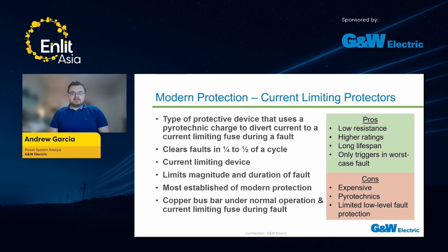These can go up to much higher ratings than the solid state breakers or the current limiting fuses can. So a lot of times it's between this and reactors at higher levels of ratings. They have a long lifespan. It's a very simple but genius electronics and pyrotechnic device, so it can last 20 years plus. And since it's electronically activated, it's only going to trigger in the worst case fault scenario. So you don't have to worry about any kind of nuisance trips, say like with current limiting fuses that lack flexibility and only follow TCC curves.